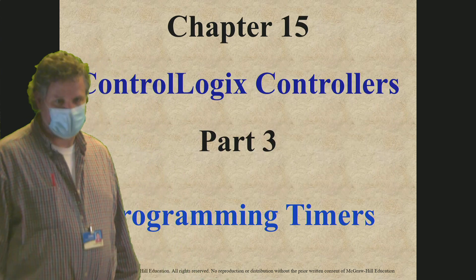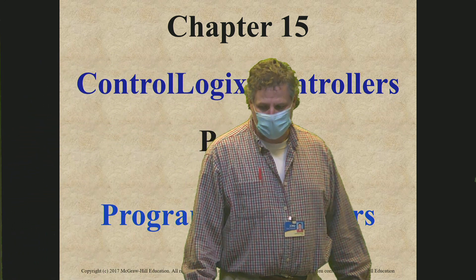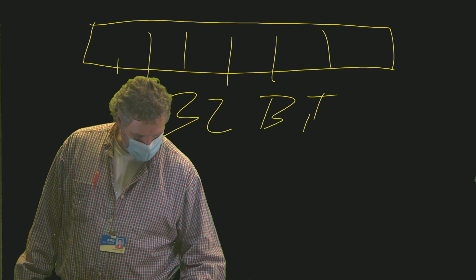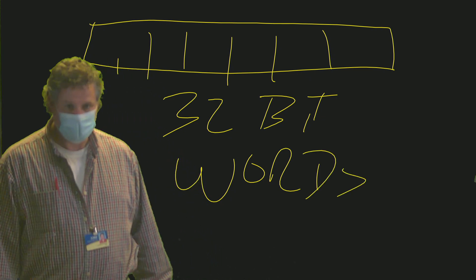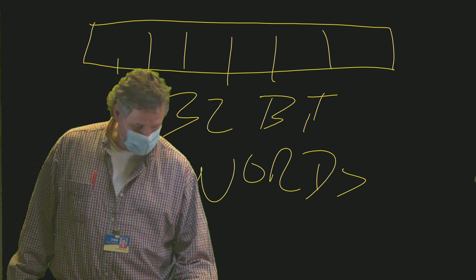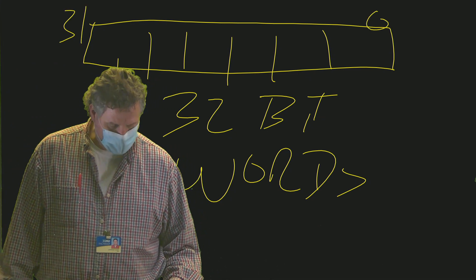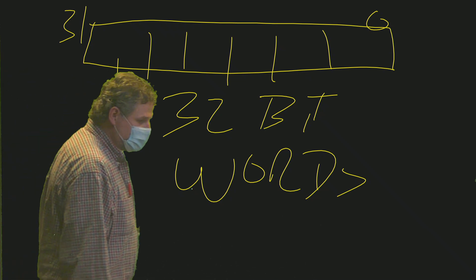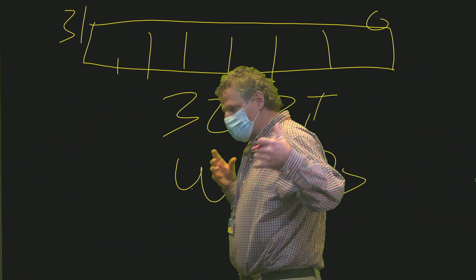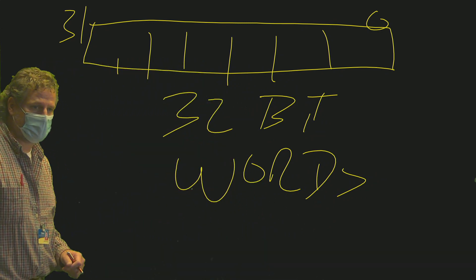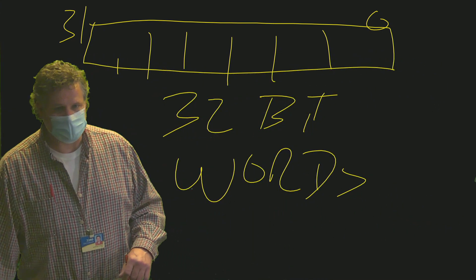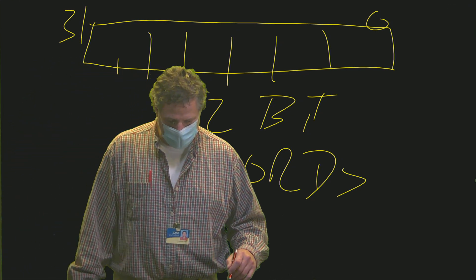We're looking at the ControlLogix controllers. The ControlLogix controller is a 32-bit based technology. When we're talking 32-bit based, what does that mean? It has 32-bit words in it — counting 0 to 31. So when we're talking 32-bit word technology, we're talking a much larger word. We can get a much larger value out of our timers. If you remember the old 500, we were stuck at 32,767 — that was the maximum value. Now we've got a value way larger than that.